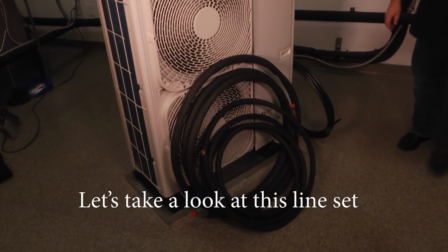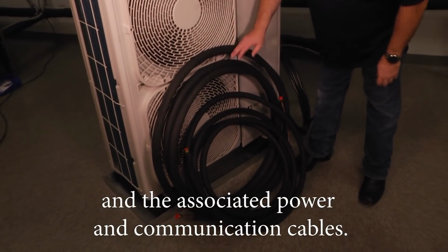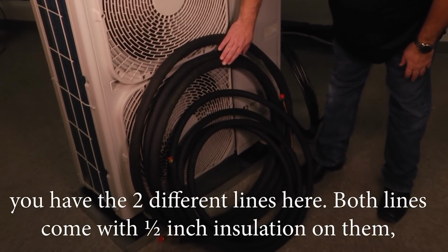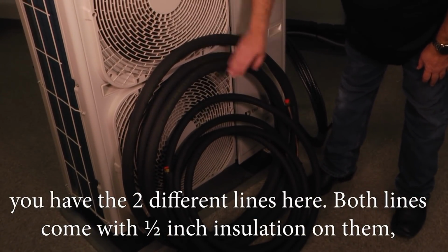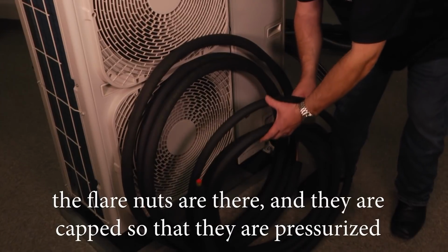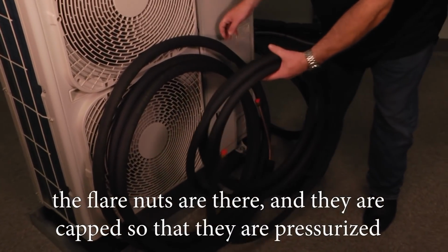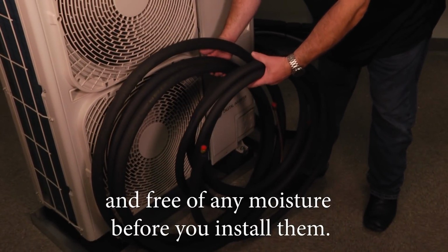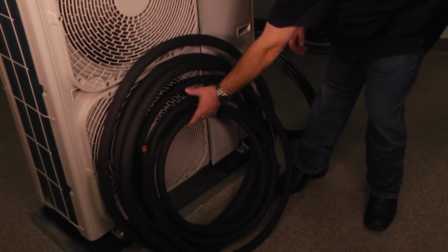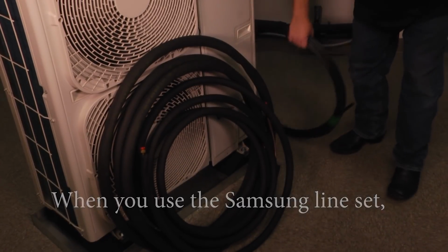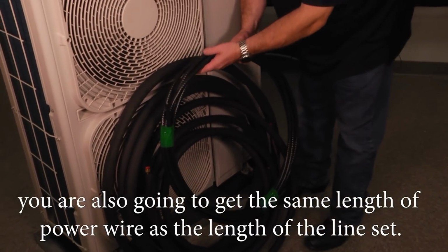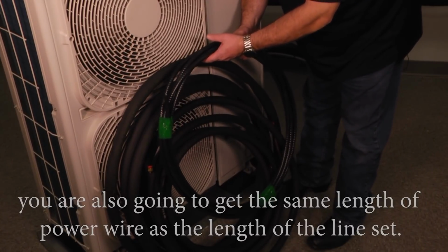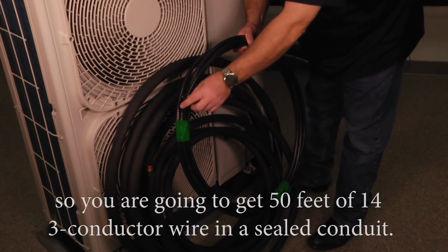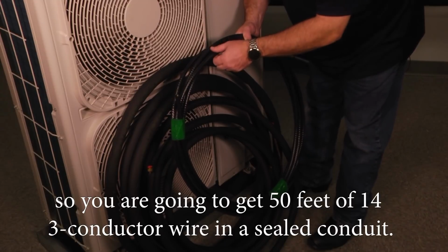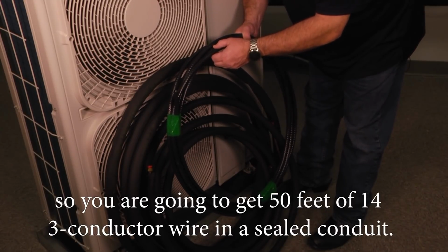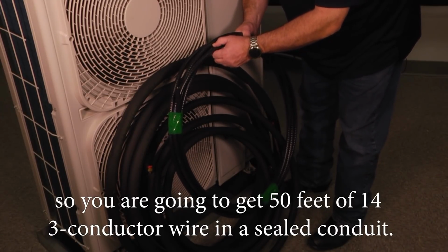Let's take a look at this line set and the associated power and communication cables. You have the 2 different lines here, both come with 1/2 inch insulation on them. The flare nuts are there, and they're capped so that they're pressurized and free of any moisture before you install them. Now when you use the Samsung line set, you're also going to get the same length of power wire as the length of the line set. So this is a 50-foot line set. You're going to get 50 feet of 14 3-conductor wire in a sealed conduit.